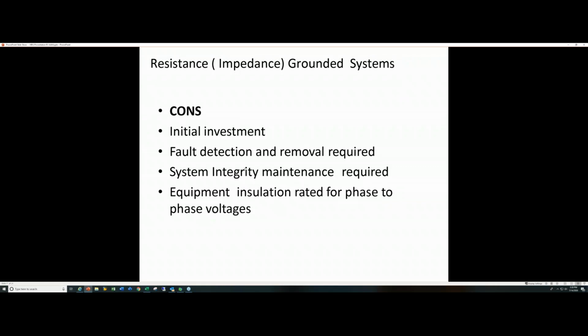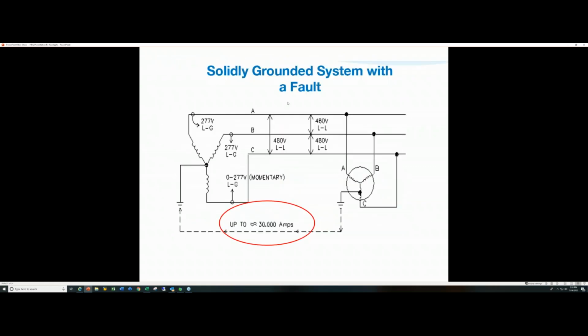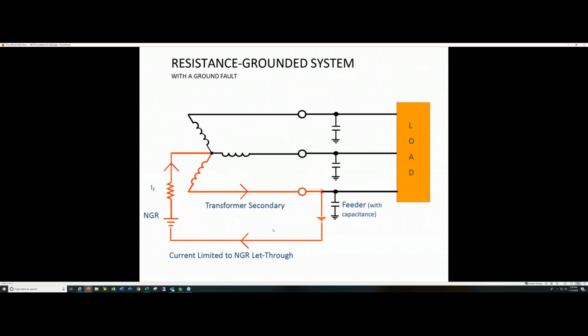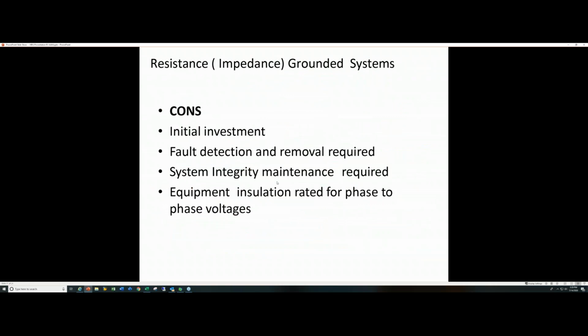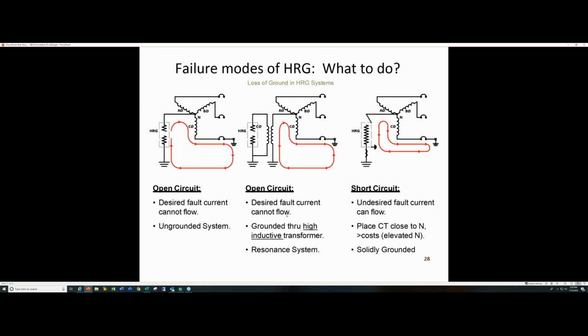So if you remember the drawing I had here, when the C phase goes to ground, and if this was on an HRG system, you would actually elevate two of these phases to a 480 volt to ground potential, while C raised up. So it's important, right, that you understand that the insulation in your system is stressed also. Not only do you have to fix it because of a secondary fault, but you got to fix it because you're stressing your old insulation in your cabling, in your bus systems, in your standoffs, in your breakers, all that. So it behooves you to get in there and fix it as quick as you can.